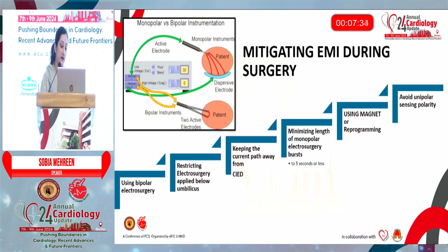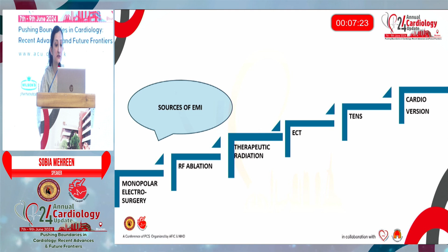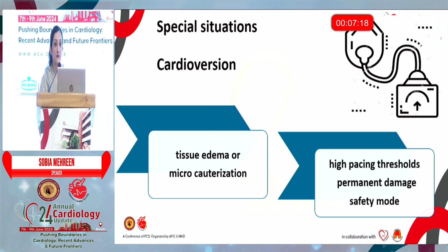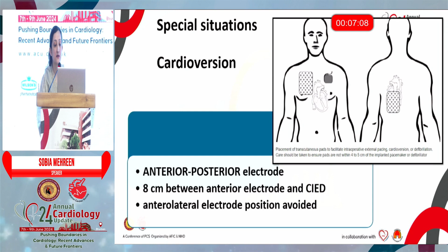The various sources of electromagnetic interference that can be encountered during the surgery are the monopolar electrosurgery, radiofrequency ablations, therapeutic radiations, electroconvulsive treatments, TENS treatment, and cardioversions. We will be discussing some of the special situations. The cardioversion can cause major hardware failure, and it can be avoided by placing the electrodes in anterior-posterior position with at least 8 cm between the anterior electrode and the device.